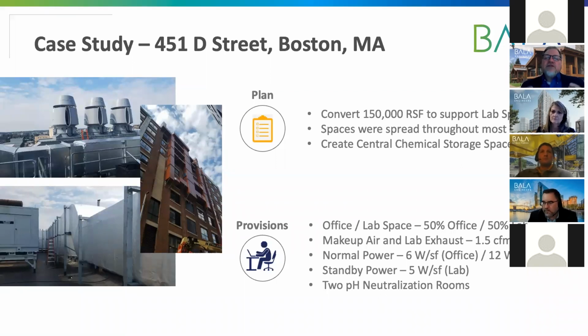On this one we put in 2 pH neutralization rooms because the building was so long, and because the ceiling floor-to-floor heights were shallow, by the time you run that pipe and slope it across the whole building, you're going below your ceilings. So it was more effective to run 2 vertical acid neutralization risers that they could tie into closer, going into 2 separate rooms.